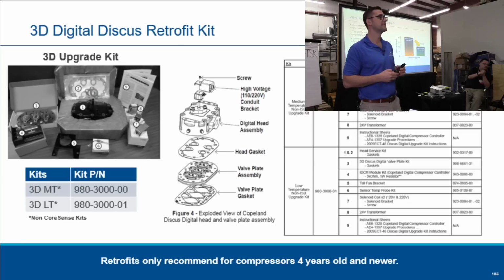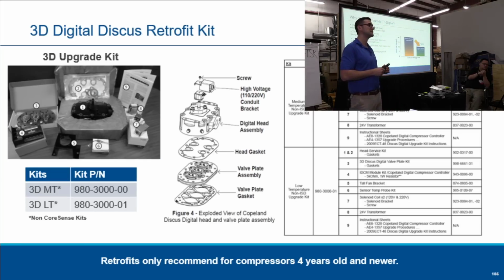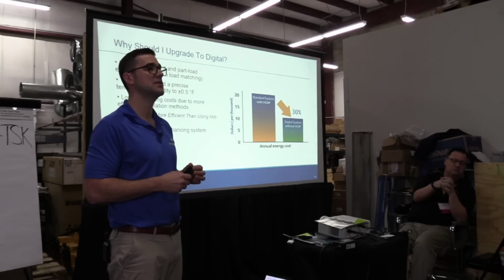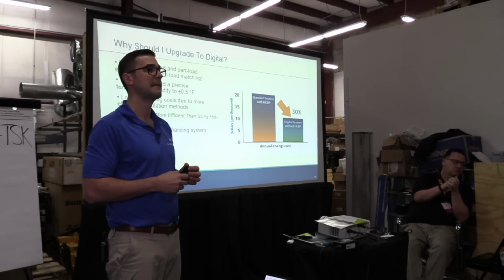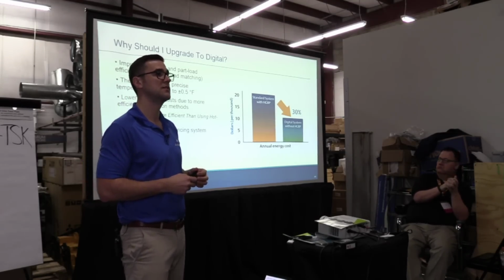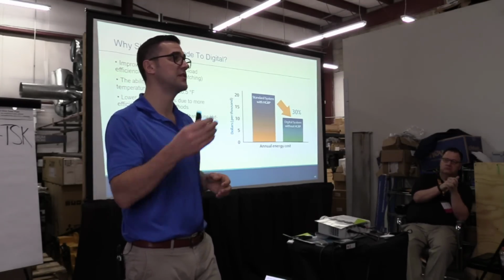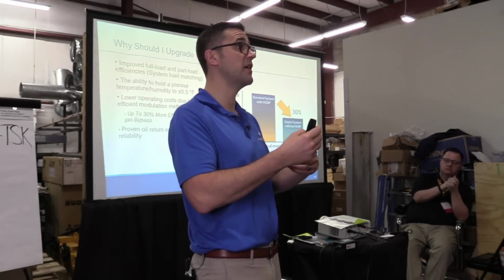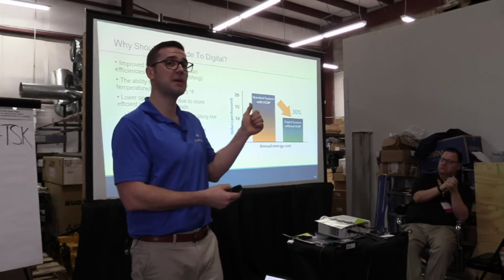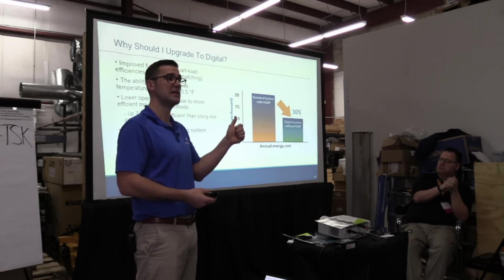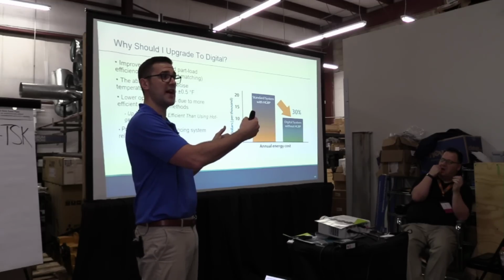Go ahead. It's basically just when, so this is not for the defrost, right? This is just for head pressure control? Yeah, it's basically when you bypass before the condenser. You bypass, go into the evaporator, put the load on the evaporator, so that system keeps running. So what's that compressor right now? Is that fully loaded? I'm putting fake load on that evaporator so it keeps running.